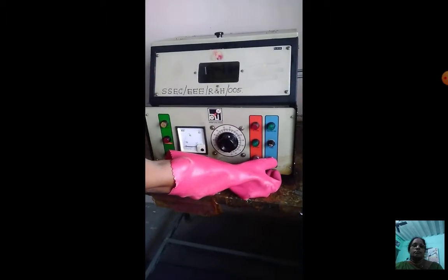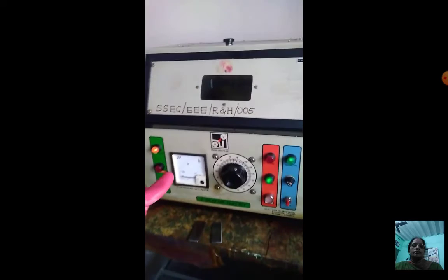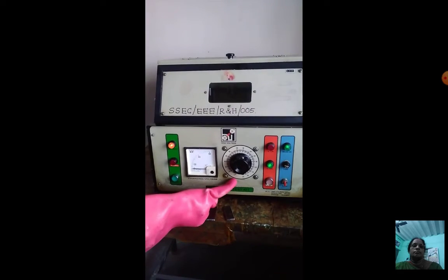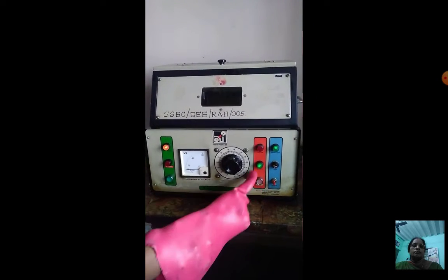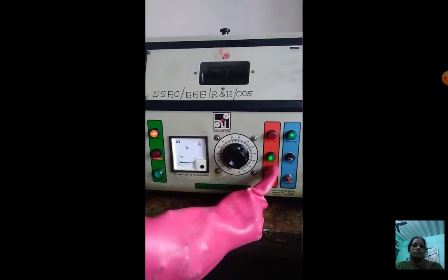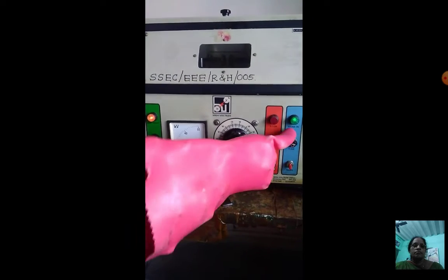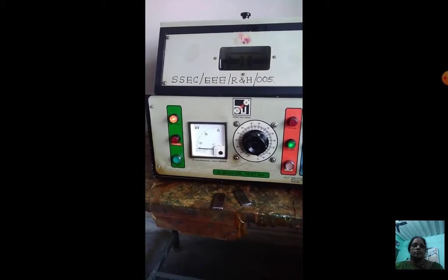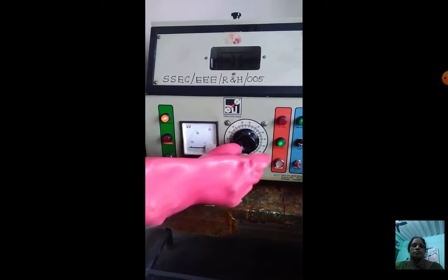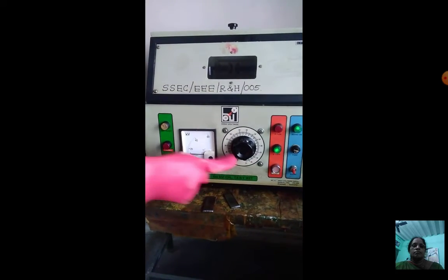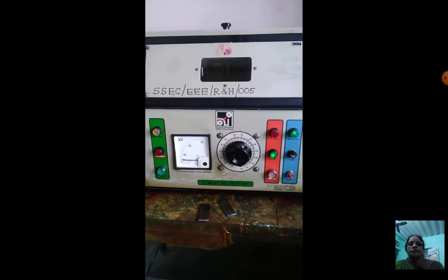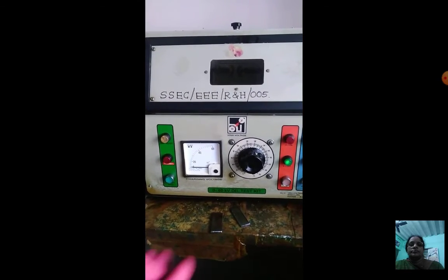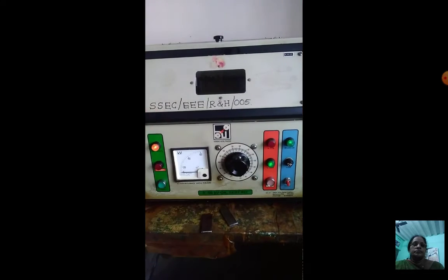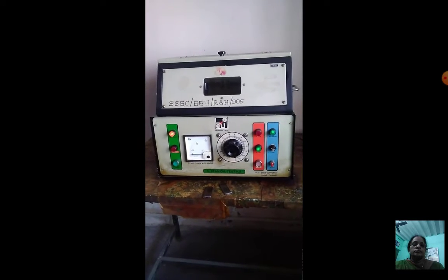Close the door. After that you can switch on the power supply. Then you can switch on the main switch. Now you see the auto transformer is in the 0 position. Therefore the high tension off indicating lamp is glowing, and the main also is glowing. The test kit is ready for the experiment. Suppose the auto transformer is not in the 0 position; then automatically the unit ready indicating lamp is switched off. Now this is the proper position. This is the first safety precaution.